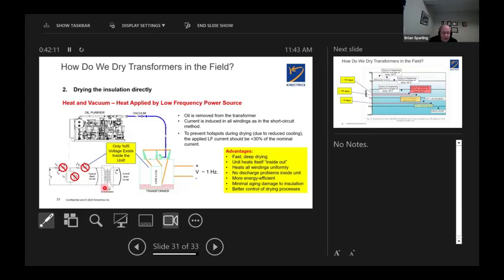So you can apply 300 or 400 amps. And that's a function of the design of the transformer. That's figured out beforehand. So the windings are always heated. So it's always pushing the moisture out of the paper and into the oil. And then time comes to evacuate all the oil, and then a vacuum is applied. But it doesn't get cold again. Heat is still going, current is still flowing to the windings. So you're still pushing the moisture into the vacuum from the windings under a vacuum, because you don't remove the power supply. You don't remove that 1 hertz supply. So you're heating all the windings uniformly. It's a much faster, more energy efficient way of doing it. And you minimize any aging due to damage to the insulation system by virtue of a controlled temperature and a better control of the drying process.